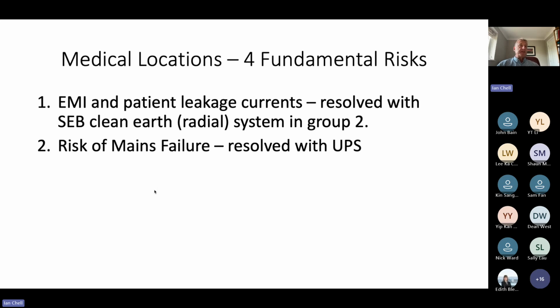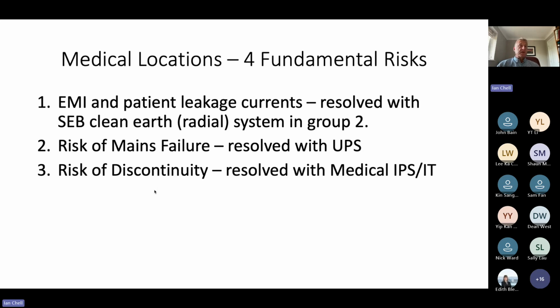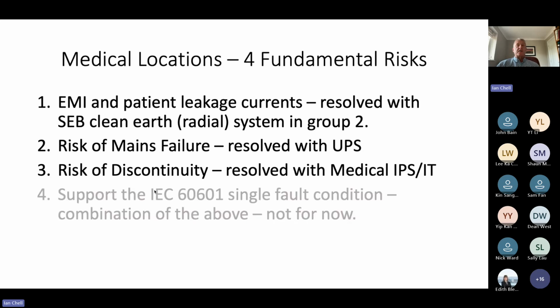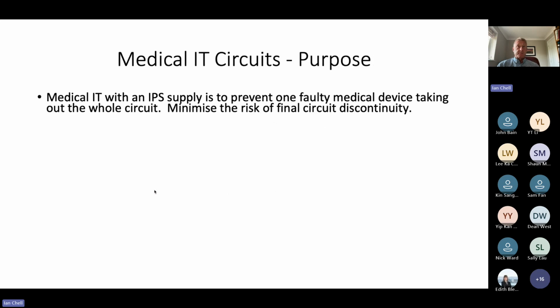The risk of mains failure is resolved with UPS. The risk of discontinuity is currently resolved with medical IPS and IT circuits. Okay. Now, I'm not going to talk about it today because it's too much, but I also feel that the other risk is to support the IEC 60601 single fault condition, which is just a combination of the above, but not for now. So that's three big risks that we have to deal with in a medical location.